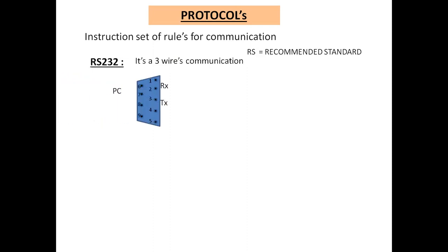You can see some connectors — a nine-pin connector in a D-shape — one on the PC and the other on the PLC. Out of these nine pins, pin number two is for receiving and pin number three is for transmitting. When transferring or receiving data from one end to another, pin two to pin three — that is what is known as 232.